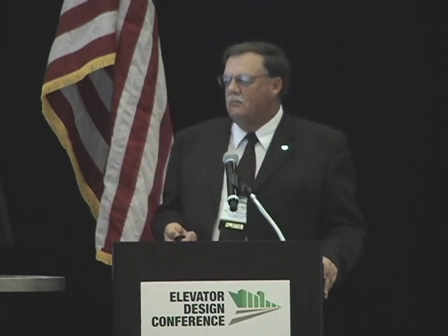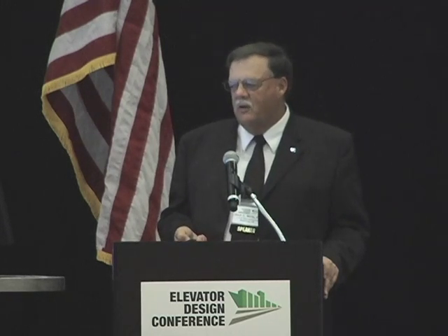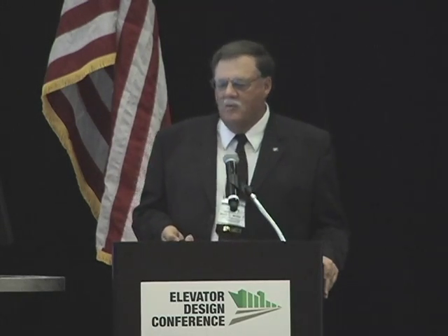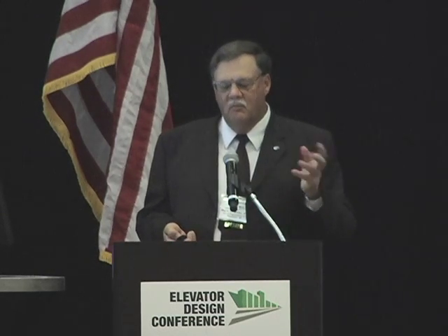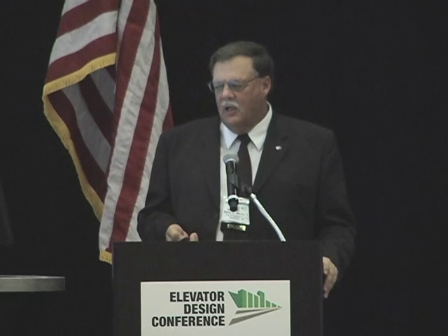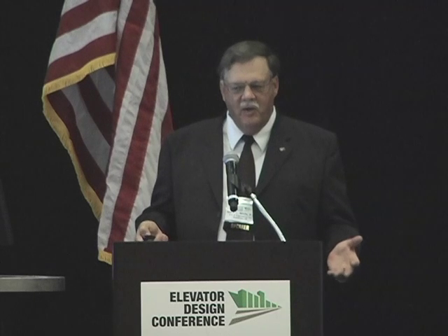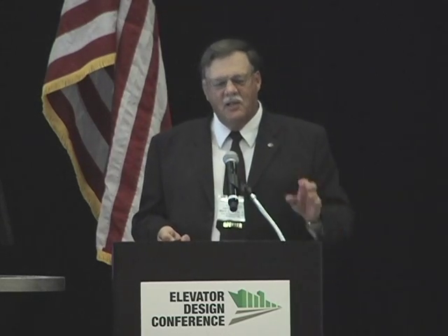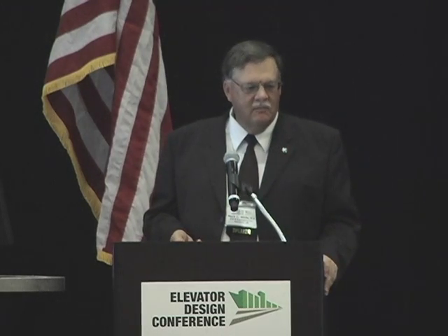One thing we do when we do have the hazardous locations is we try to put our major equipment, if they're in the area, in pressurized rooms. And fortunately, in a dust hazard area, it's very easy to get a clean source of air and pressurize the room. You only need 1/10 of an inch static and certain velocity requirements if you open the doors. And if you pressurize the room with a clean source of air, it's non-hazardous. And so you can put anything you want in there. So the basic technique is get those load centers, stick a room in your shipping gallery and pressurize it.